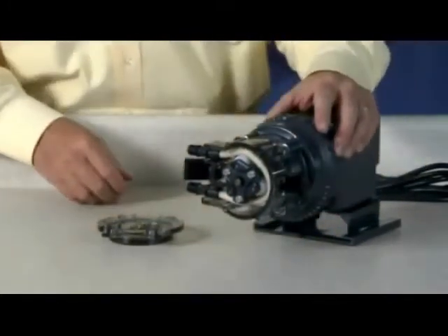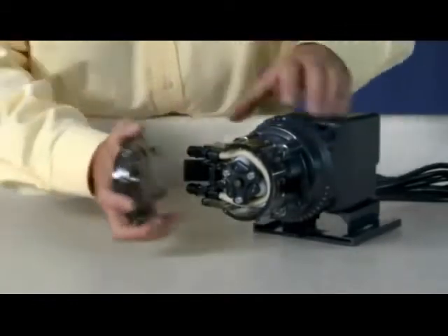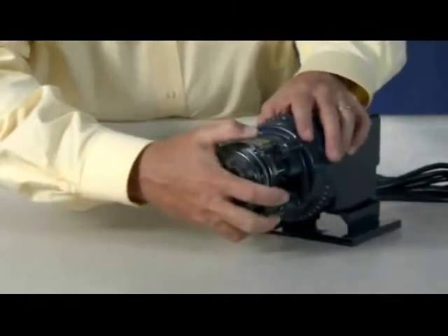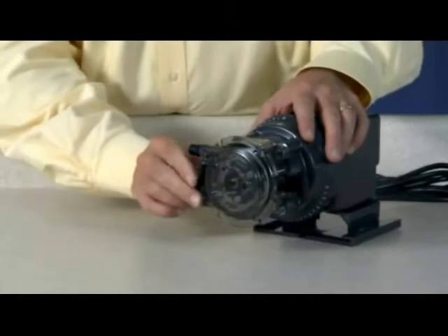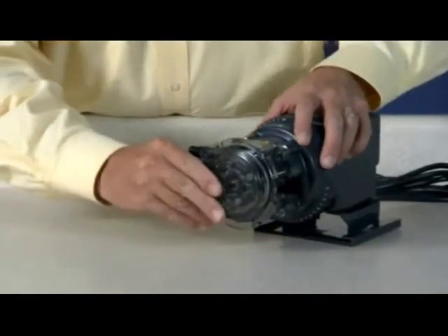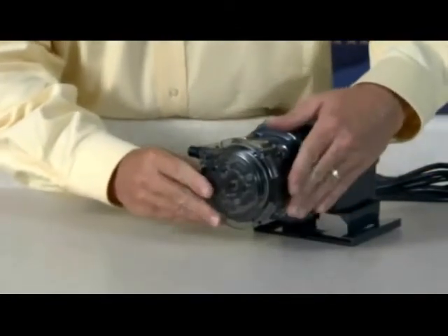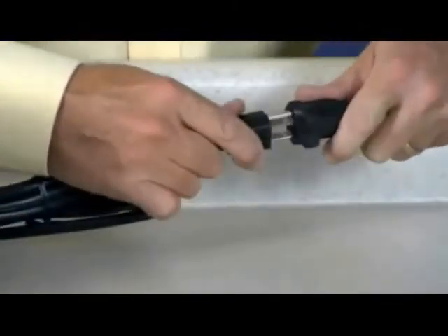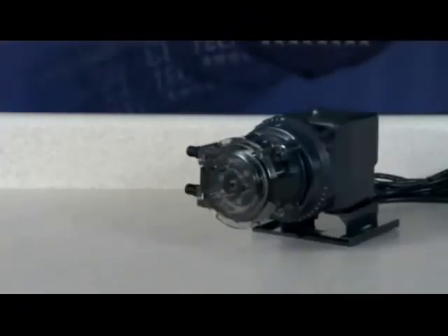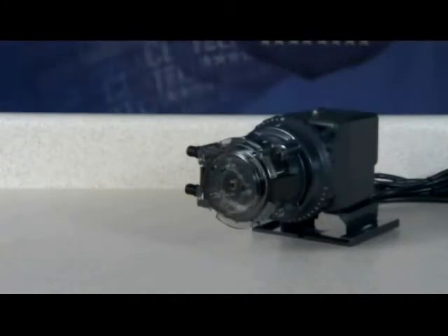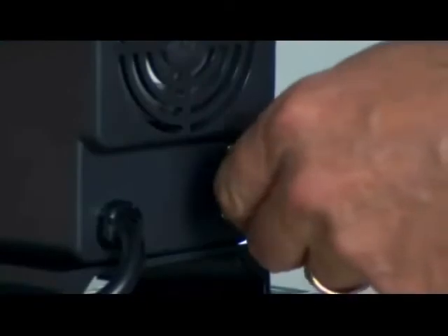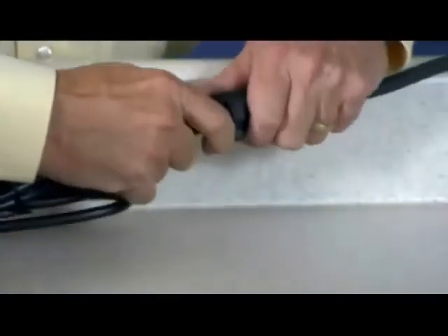Place the tube housing cover, feet first, on the tube housing. Affix the front of the latches to the cover lip and then press the latches back to secure. With the cover latched, plug the pump in and turn it on. Allow the pump to run the roller assembly in its collapsed position for approximately 1 minute to relax the tube. Turn the pump off and unplug the power cord.